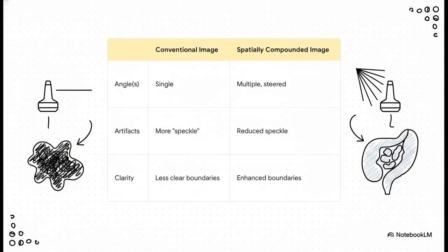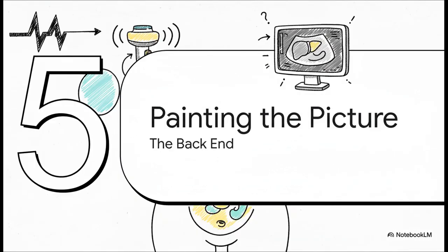And the high-end systems have even more tricks, like something called spatial compounding. Check out the difference here. On the left is a conventional image, taken from just one angle. It's okay, but kind of grainy, right? Now look at the right. That's a compounded image. The machine took pictures from multiple angles and stitched them together. Bam! The speckle noise is reduced, the edges of the tissue are way clearer, it's just a much, much better image. Okay, at this point, we've got clean, amplified, and perfectly organized data.